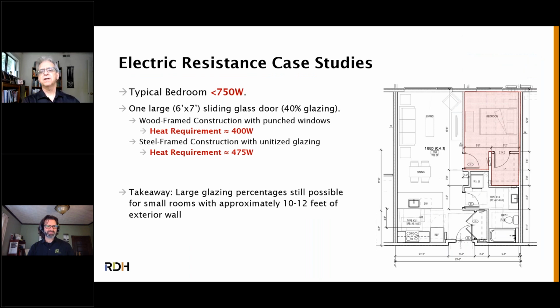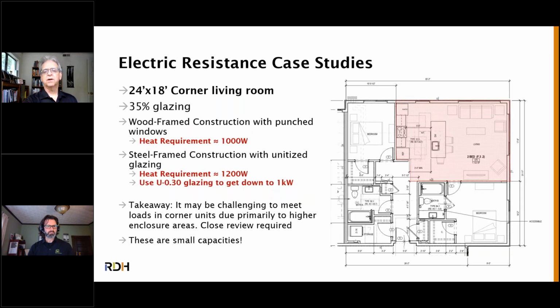And somebody from RDH looked at heat loss through the walls. A typical Seattle apartment building with a big slider as its window is coming in below 500 watts. If you've got a larger room on a corner, it's coming in at 1,000 watts for wood frame or 1,200 for high rise. So even there, where you've got 1,200 for high rise, it's going to be a lot cheaper to just do high quality glazing. Maybe go to triple glazing and it'll cost you an extra $1,000 or something like that, and your 1,000 watt allowance would cover that. So look carefully at your heat loss numbers, but if you don't want to do a heat pump, all you have to do is be really careful about how you design your building envelope.